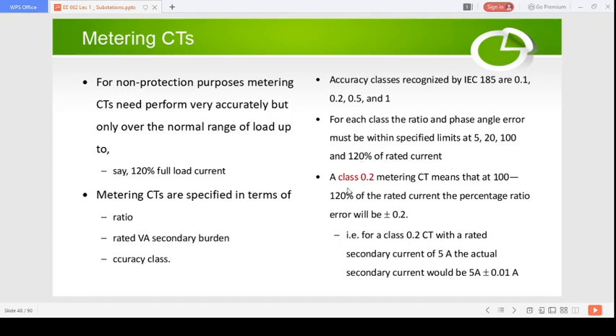current. A class 0.2 metering CT means that at 100 to 120% of the rated current, the percentage ratio error will be plus or minus 0.2. So that's what is defined by 0.2. That is for a class 0.2 CT with a rated secondary current of 5 ampere.